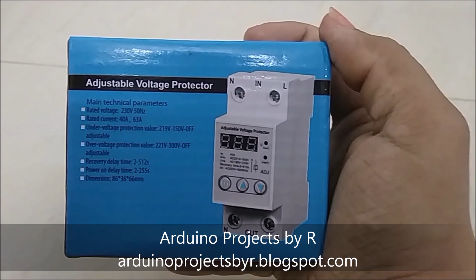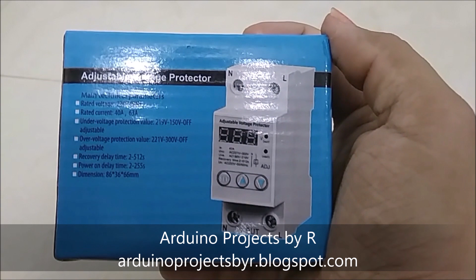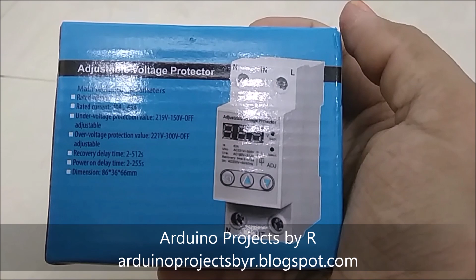The power on delay time is 2 to 255 seconds, meaning when there's an undervoltage protection and the adjustable voltage protector is to give its output value, it has to be switched on, and the delay time is between 2 to 255 seconds. Its dimension is 86 by 36 by 66 millimeters.